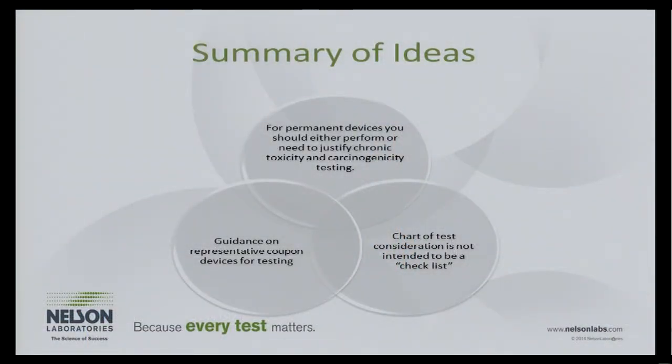This is another one that makes me smile. It actually says in there that the chart in ISO 10993 and in this new draft document is not intended to be a checklist, okay? The FDA does not want you just to go down and check, do all the tests. I still have people who do that because they think it's safe and they'd rather just do that than risk anything. But the FDA really does want you to evaluate the need for the testing on your device and justify why you're doing those tests and why you're not doing other tests. They want you to take a scientific approach and not just throw the phone book at it, so to speak.